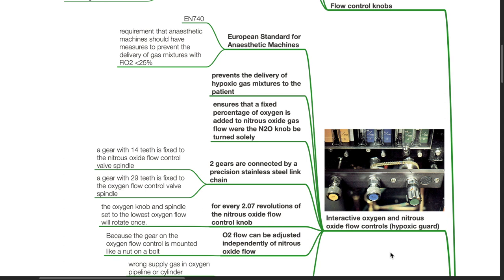Interactive oxygen and nitrous oxide flow controls, also known as the hypoxic guard. It is a European standard for anesthetic machines, EN740, requirement that anesthetic machines should have measures to prevent the delivery of gas mixtures with FiO2 of less than 25%. This hypoxic guard prevents the delivery of hypoxic gas mixtures to the patient.